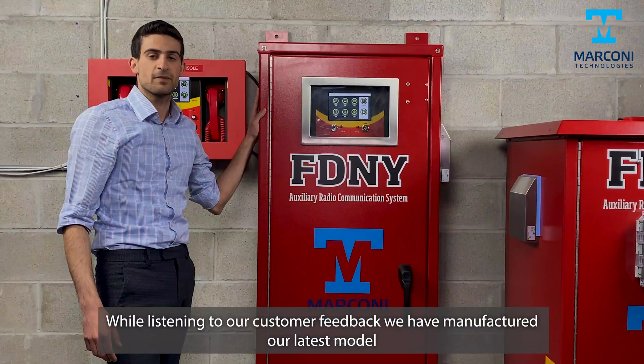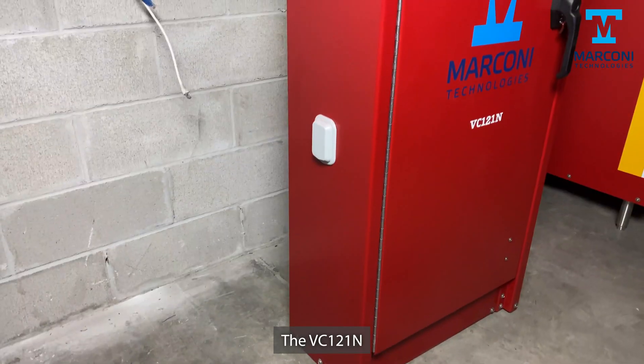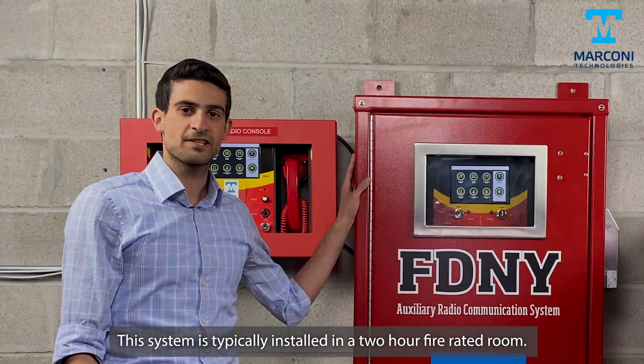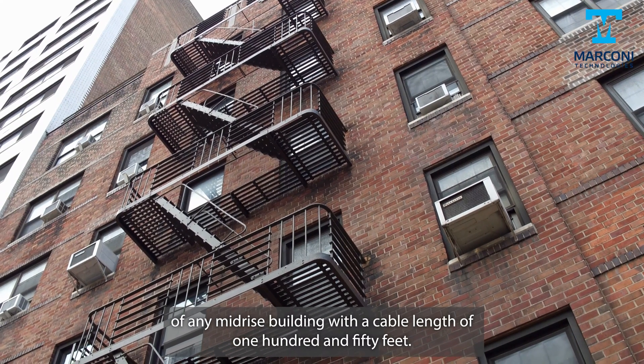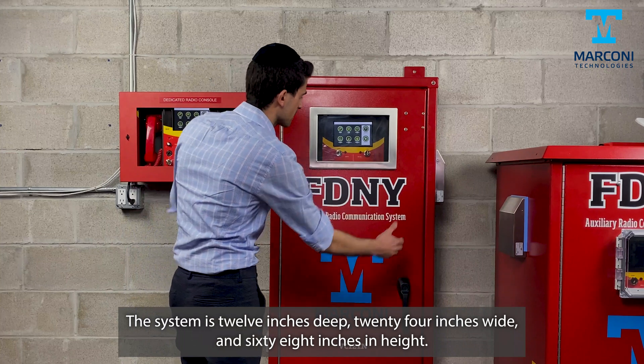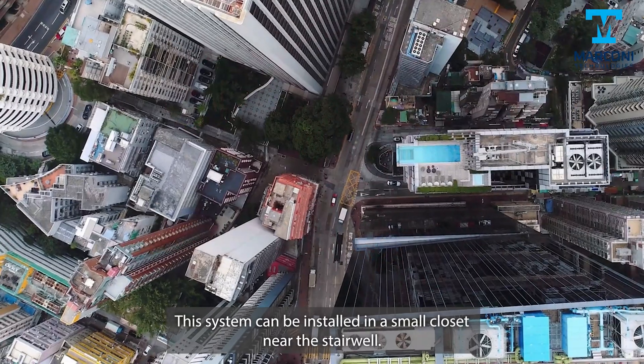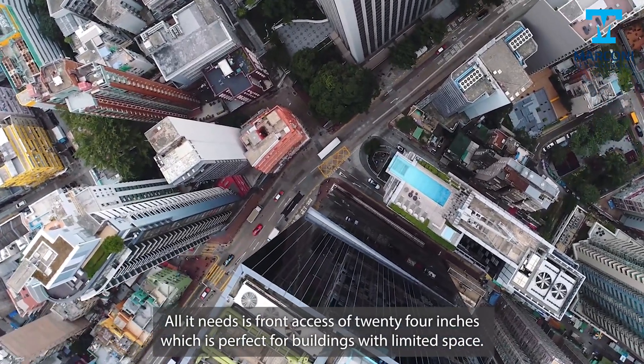While listening to customer feedback, we have manufactured our latest model, the VC121N. This system is typically installed in a 2-hour fire-rated room for any mid-rise building, with a cable length of 150 feet. The system is 12 inches deep, 24 inches wide, and 68 inches in height. This model does not require rear access and can be installed in a small closet near the stairwell. All it needs is 24 inches of front access, which is perfect for buildings with limited space.